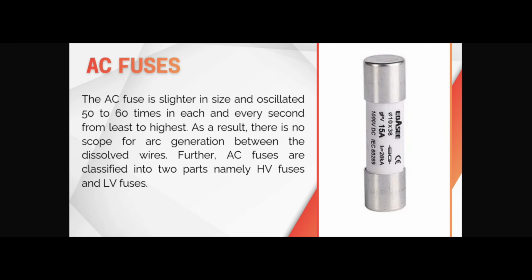Kagaya ng ibang fuses, may metal strip din sa loob nito na natutunaw when the current flow is too high. In AC current, the direction of current changes many times per second, or 50 or 60 times per second. As a result, there is no scope for arc generation between the dissolved wires. It means na for AC fuses, kapag natunaw na ang wire sa loob ng fuse, the current is constantly reversing and passes through zero. Therefore, no arc or spark was generated.